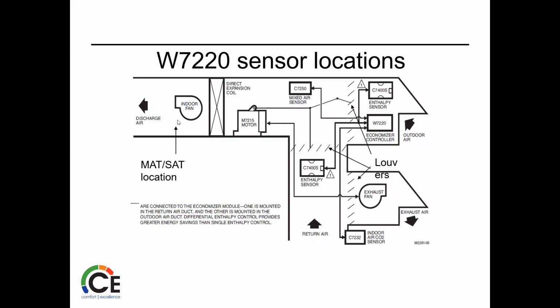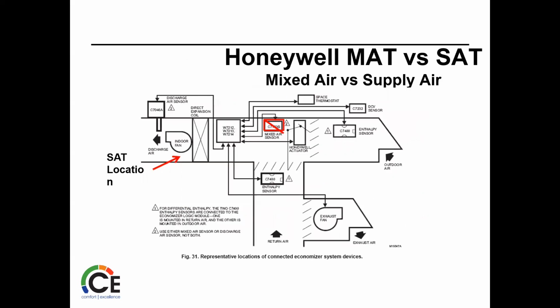So MAT location, it's always going to be in that indoor fan. Even if it's the newer style and maybe you have a vane axial fan, you're still going to locate it in that blower cabinet. The old style used to mount right on the housing, but the vane axial doesn't allow that, so we still just put it in the same location there. Mixed air supply air thermistor, obviously, that's what we're talking about, putting that there.